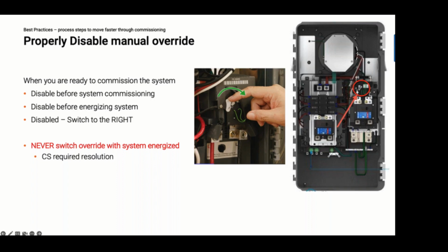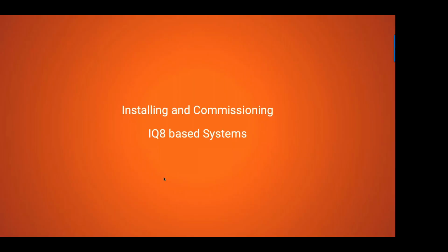If you do energize the system and have forgotten to disable the override switch, do not flip the override switch with the system energized. Doing this will signal an error in the system that can't be cleared unless you call the support line. Now, to flip the override switch after the system has gotten power to it, you have to de-energize the system. Remember to tell the homeowner you're going to do this. Turn off all power, allow the system to rest for 1 minute to discharge capacitors in the system controller. After the 1 minute wait, then you can disable the override and then re-energize the system. All right, so those are probably the highlights in terms of installing our energy storage system and commissioning. If you pay attention to those, I think it'll really benefit you a lot.